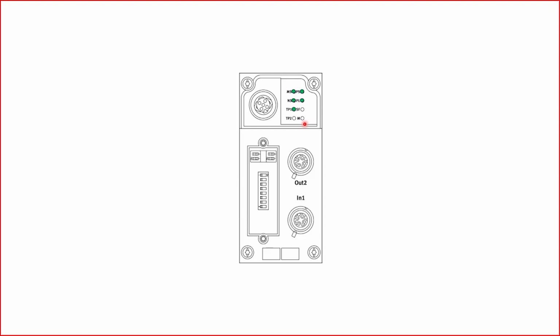If you have a flashing yellow light on the manual or modify LED, this indicates that forcing is active, meaning that using one of the Festo provided software, you are manually controlling the inputs or outputs that are connected to the CPX field bus node.